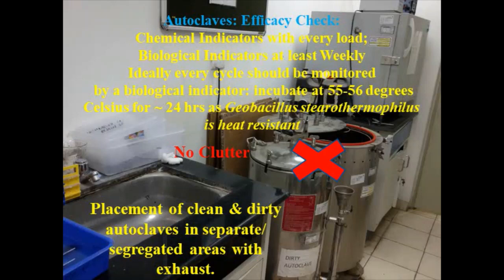So all laboratories should have a water bath or an incubator set at 55 or 56 degrees Celsius for incubating the biological indicators after they are used in the autoclaves, and these should be incubated for at least 24 hours. These biological indicators contain the spore strip, that is Geobacillus stearothermophilus spores on a strip of paper, which is in the outer plastic jacket, and inside it contains a glass vial which contains the media, and this media is usually purple or violet colored.